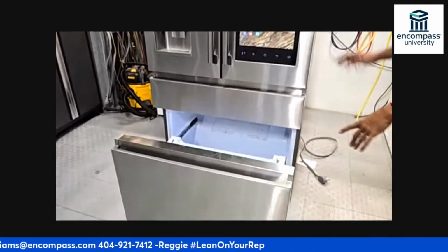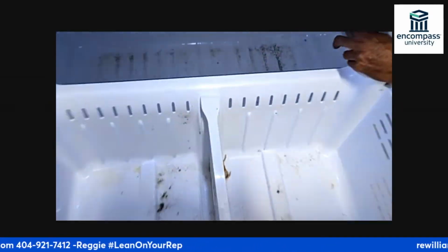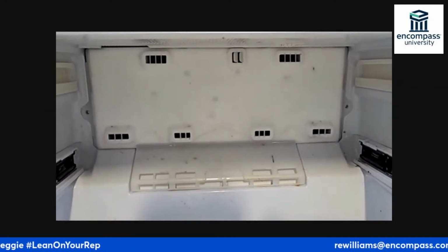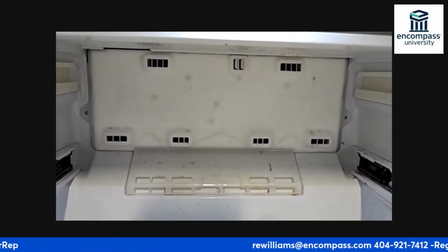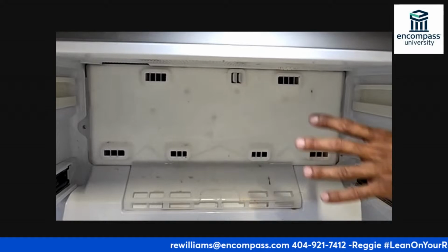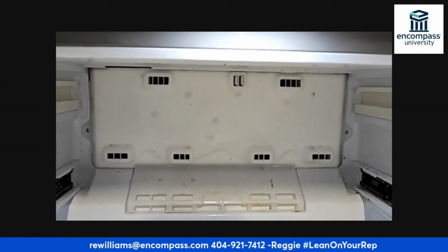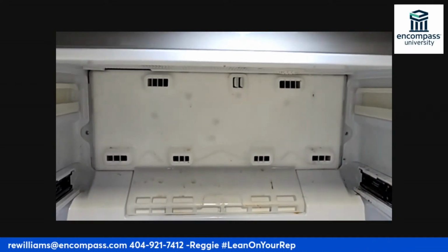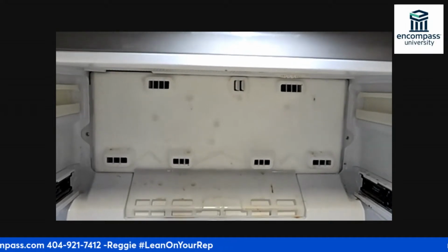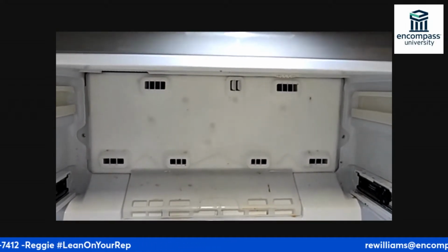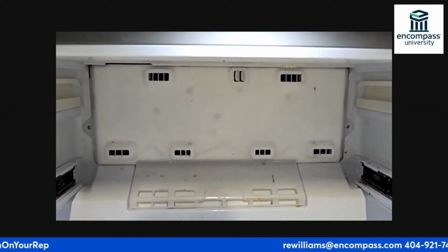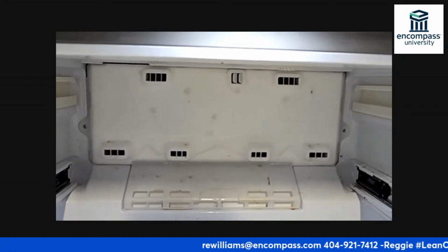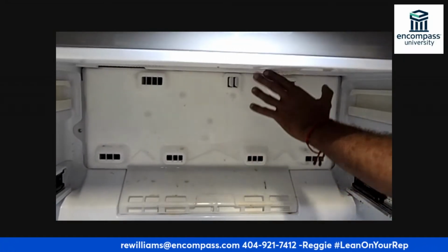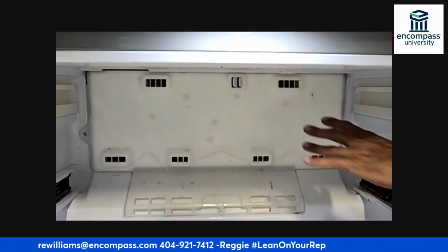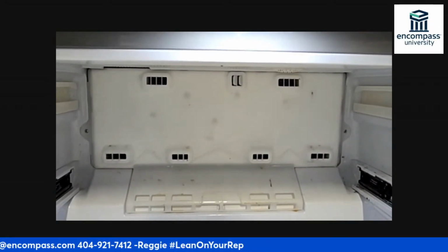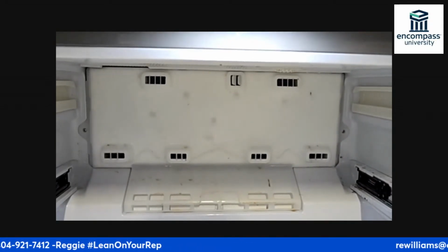Look right here, we're going to come down and look at this evaporator cover. Is my cover frosted? Do I see a bunch of ice buildup back there — snow, if you will, not ice, because ice is water that has frozen. I don't want to look for ice, I want to look for snow. If I see my rear evaporator panel completely full of snow, then I know I'm in trouble — I have a defrost failure.